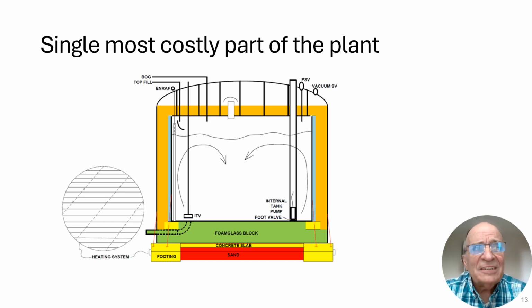That's the least popular because you have to deal with pump seals, and the potential that if you have a seal, you could have a leak, and then there are problems associated with that. Many of the pumps that are external to the tank are actually motor and pump submerged in a liquid inside of what's called a pump can. So these are the exact same types of pumps, but instead of being installed in a tube that goes into the tank, they're installed in a can that's outside of the tank.